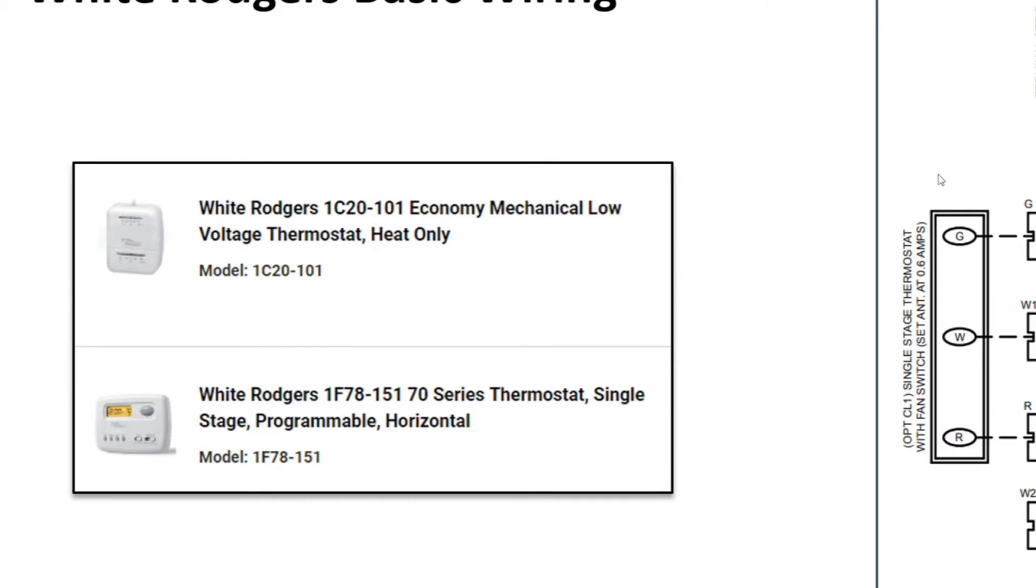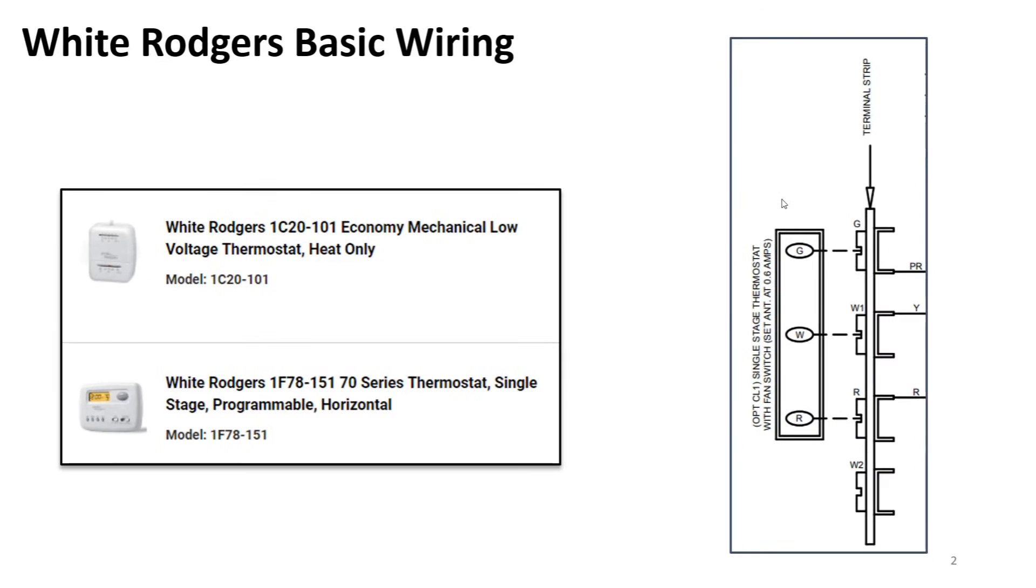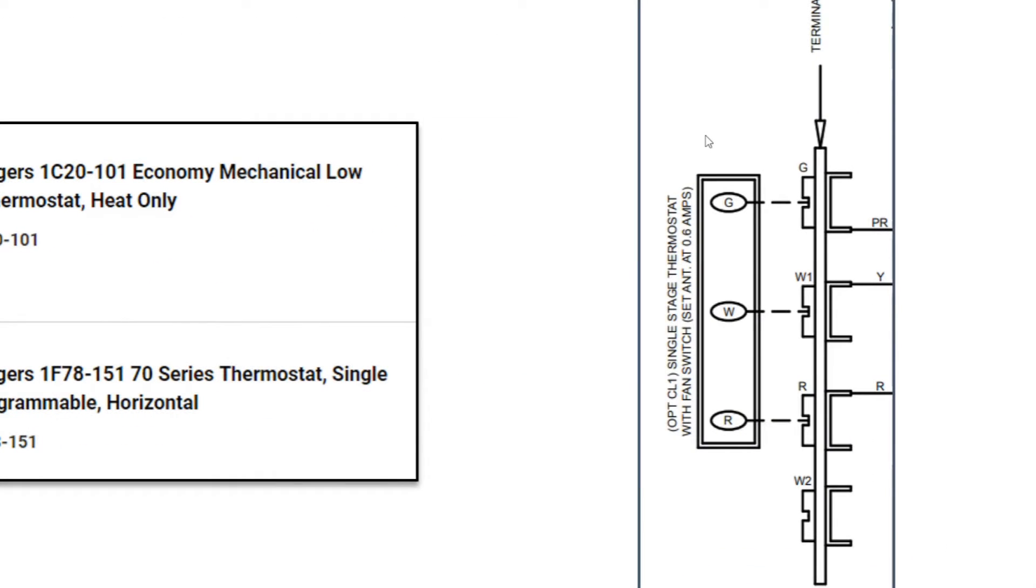Long and short of it is it does allow you to do that three connection points, so it'll have a G, it'll have a W, and an R. The R and the W, or RH and W1, that is for completing your circuit for heat. The G is what you're going to use for the fan, and that White Rodgers programmable thermostat will have a fan switch on it so you can flip that on on a hot day in your garage and it'll provide some airflow throughout the building.